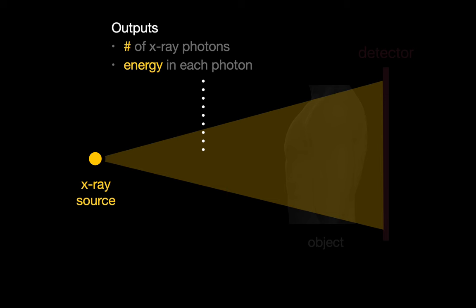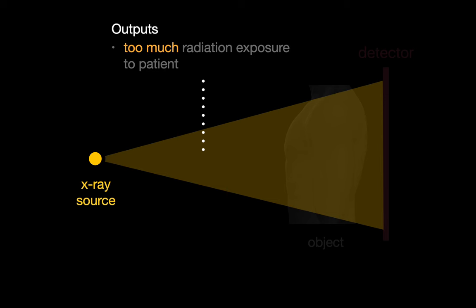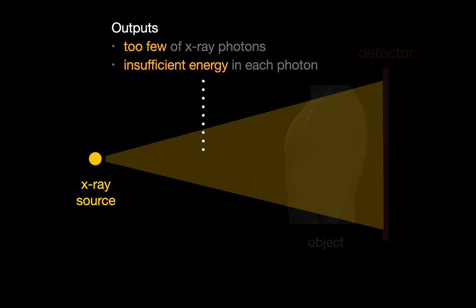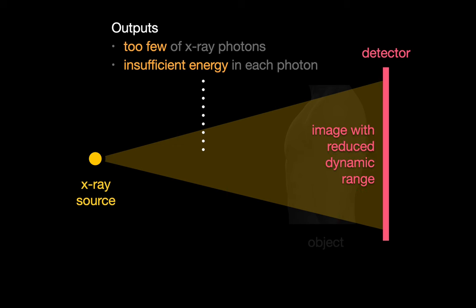Since not every patient is the same size, the optimal amount of current and voltage may vary from patient to patient and needs to be correctly selected. If we deliver too high a current or voltage to our x-ray tube, we may end up delivering too much radiation to our patient. While if we choose too low a current or voltage, we may get a noisy image since there's not enough x-ray photons to make our image with, or we may end up with an image with reduced dynamic range, which can make it hard to distinguish one anatomical structure apart from another on the chest x-ray.